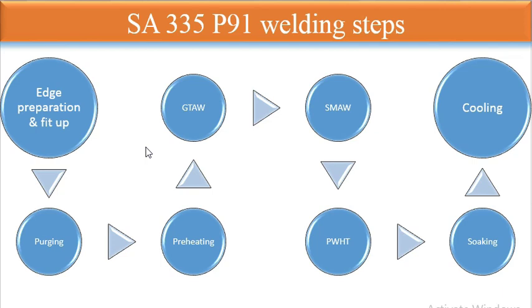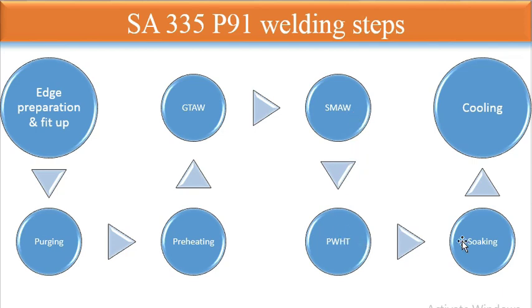The SA335 P91 welding steps are as follows: first, edge preparation and fit-up; then purging; then preheating; then GTAW — starting with the root pass, then filler and cap passes; then SMAW for subsequent passes; then post-weld heat treatment (PWHT) for stress relieving; then soaking; and finally cooling. After completing this full process, the welded joint is ready for service.